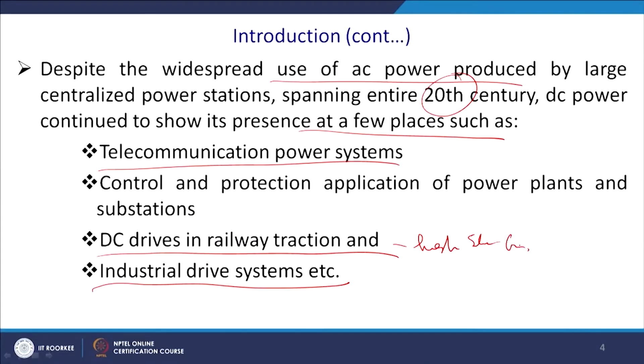Now the development of power electronics comes into the picture. It also enables AC systems to have those features, like V/F control, and thus you can have varied speed at a constant torque. If you require a high starting torque, that is also possible by V/F or vector control, and independent control of torque and speed is also possible, like a separately excited DC motor, in the induction machine by vector control. That is where the role of power electronics comes in, fitted to the front end of the induction motor.